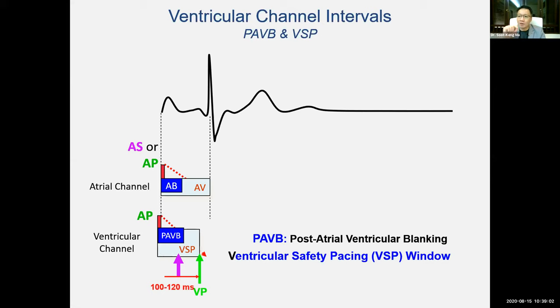This is especially important for patients who are dependent on pacemaker at a ventricular level, for example, complete heart block. If you have an event detected at the ventricular level, although it falls into the ventricular refractory period, it must be handled with care, because if you see it and think it's just another intrinsic cardiac activity which you ignore, you may, at the end of the refractory period, pick up another signal that initiates another timing cycle, so the pacemaker won't pace at the ventricular level. As you know, if the patient is pacemaker dependent, this will be catastrophic for the patient.